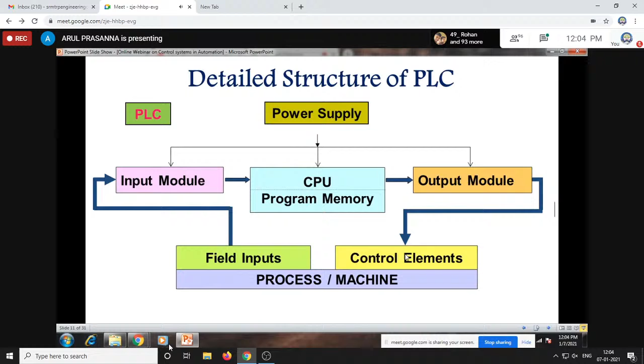So here is the input module. You have a 24 volt DC input device, and the input module converts this 24 volts to 5 volts. The CPU will receive either 5 volt or 0 volt: when you give 24 volts, 5 volts will be available at this terminal, whereas when you have 0 volt here, you will have 0 volt at the CPU.